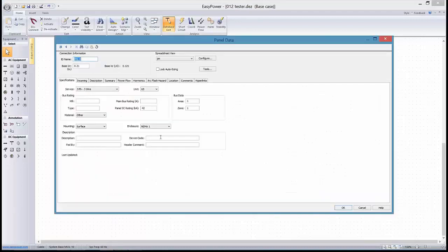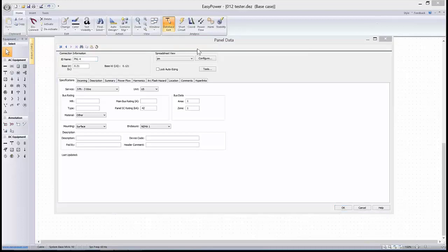Now, as we do this, what did I pick up there? We're accurately describing what the phase distribution is for these going out to subpanels. But what you'll see is we have a 210 line-to-line voltage available, and going from line to ground, we get 120 volts out of it. It's not quite the same as a split phase system that we see in residential applications, but certainly we see this fairly frequently in industrial applications.